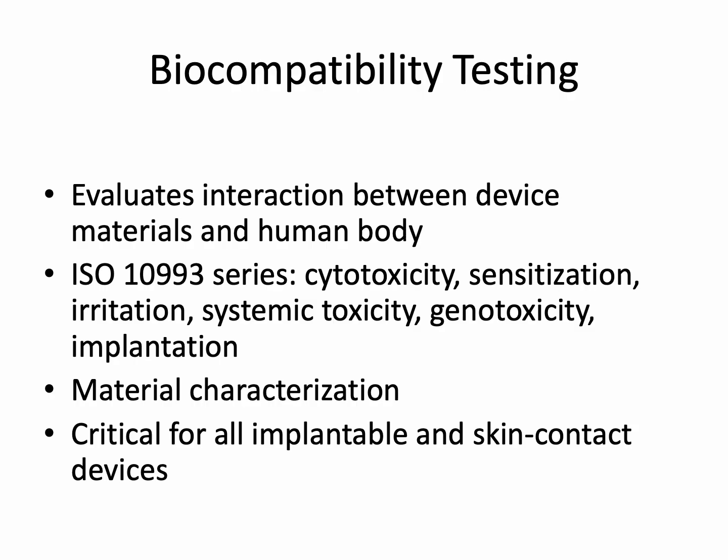Material characterization, including chemical analysis, identifies potential risks and ensures compatibility with biological tissues. Proper biocompatibility evaluation is essential for implantable or skin-contacting devices to prevent adverse reactions, satisfy regulatory requirements, and support safety claims in submissions across FDA, Health Canada, and EU MDR frameworks.